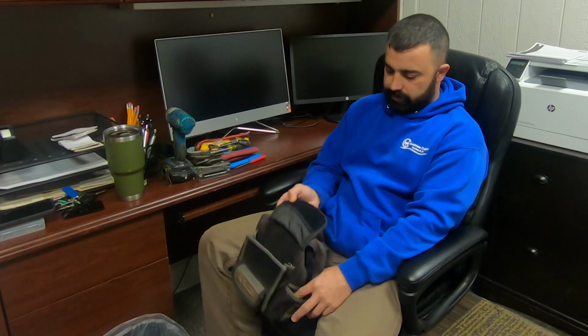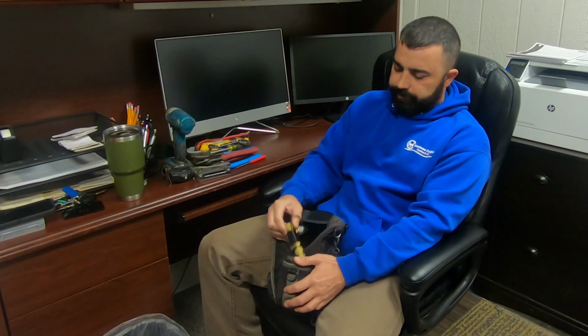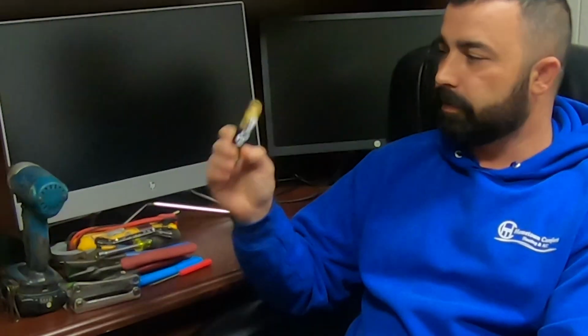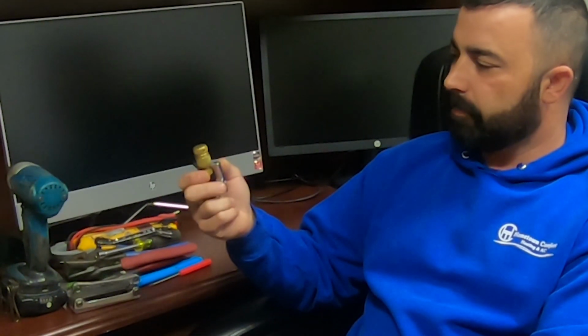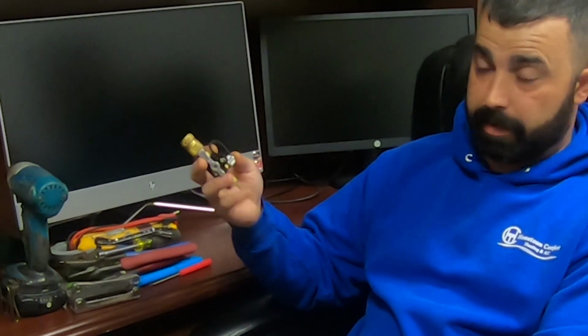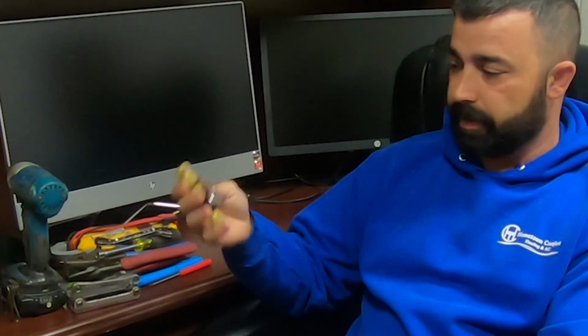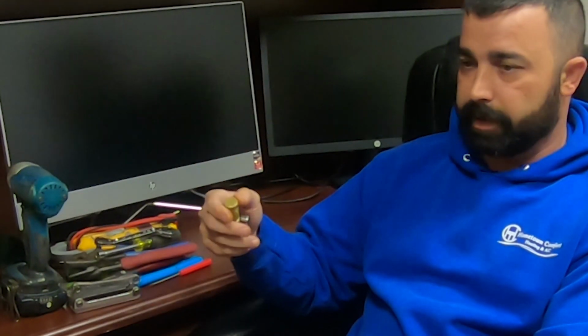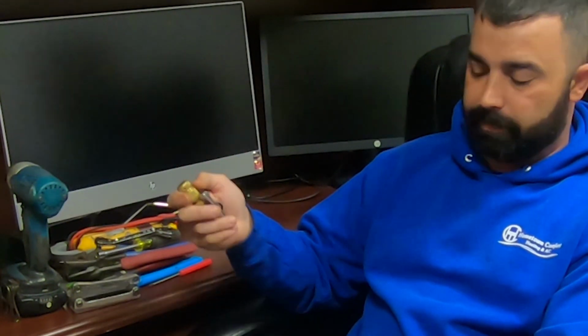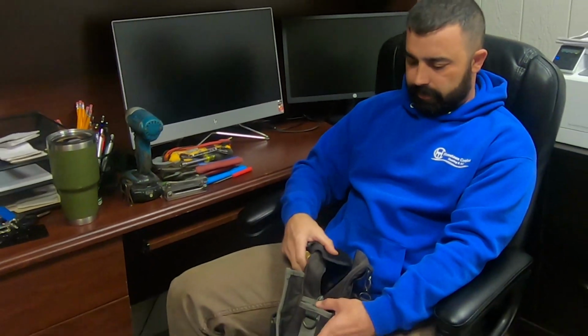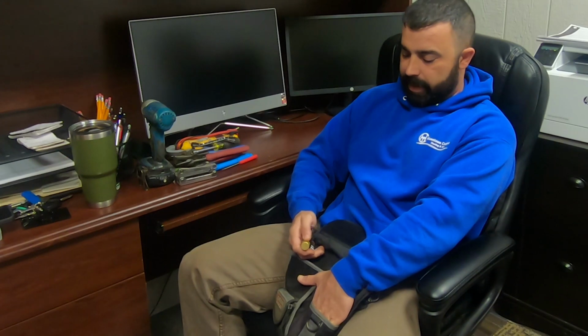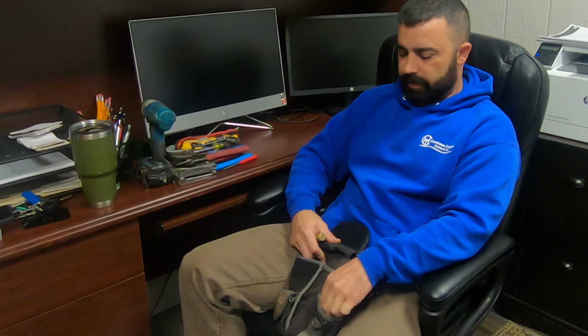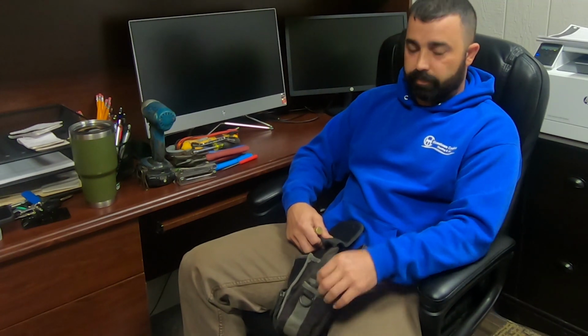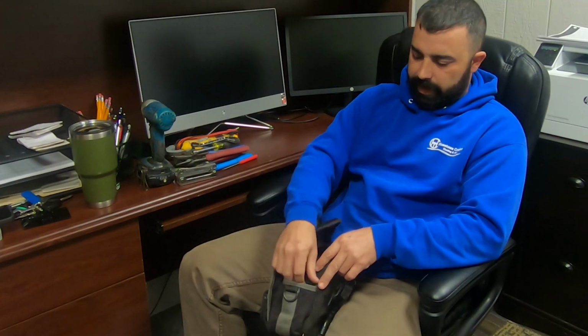Outside of that is, oh, here we go, a valve core removal tool. I use this thing a lot in the summertime. Walk up to a unit, it's low on refrigerant, you find the valve core is loose because the guy that welded it in didn't remove the valve core, burned it up, so it's leaking. Or sometimes they stick and you have to pull them out. People crank down pretty hard on their valve core sometimes, and they have to be replaced. So that really makes it handy.